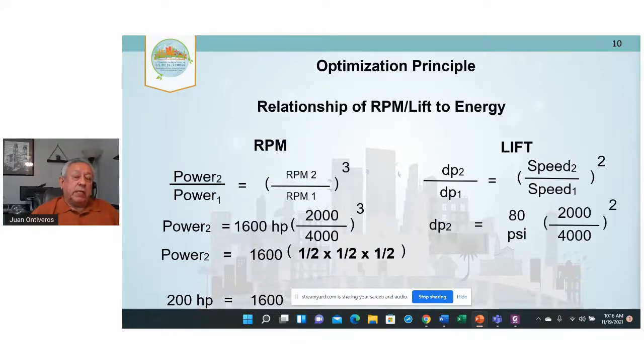Lift is similar. If I'm originally at 80 psi, and the lift I'm talking about is really the difference between chill water temperature and condenser water temperature, that's the cooling tower temperature. If I can lower the speed and reduce it to 20 psi, that's 1/4 of the pressure, so it saves a big factor in efficiency.